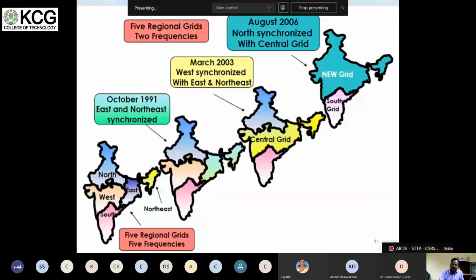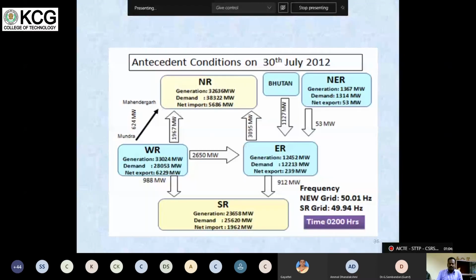2006 onwards, up to 2013, the grid was operating like this only. All four grids are together operating, called the NEW grid, and the other one is called the southern grid, which is our grid in Tamil Nadu and other states. This is a condition. During this condition only, this failure happens. So the southern region was totally separate, but it is drawing power from the WR, western region, and the eastern region through HVDC lines. Since it is a different frequency region, it cannot be connected with the AC links. That is a problem in the AC link.